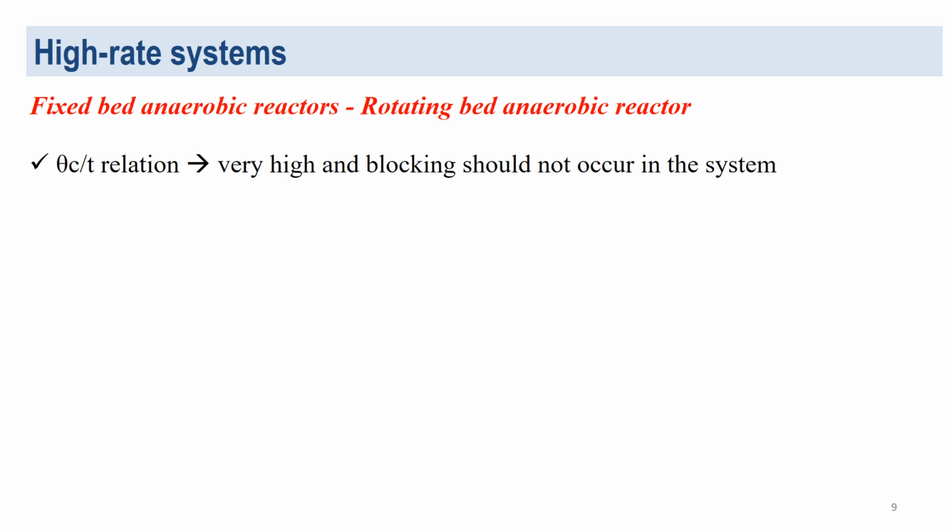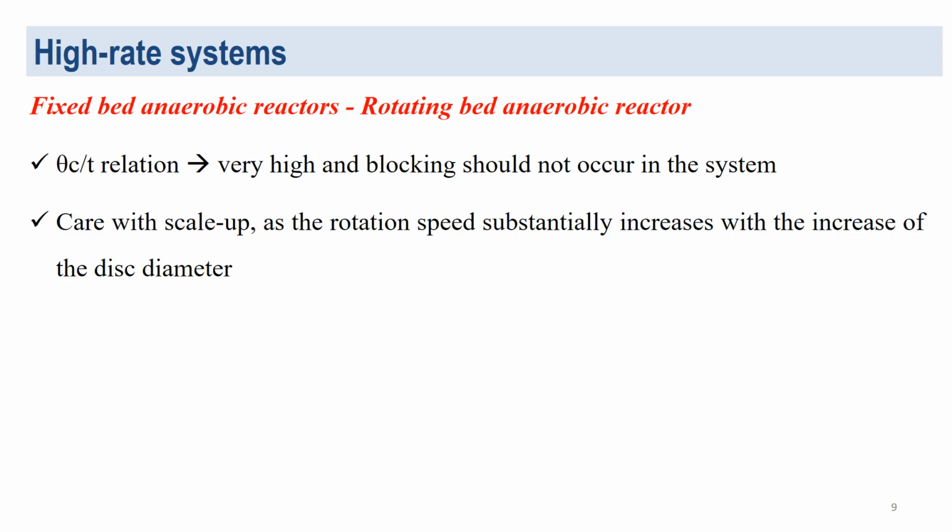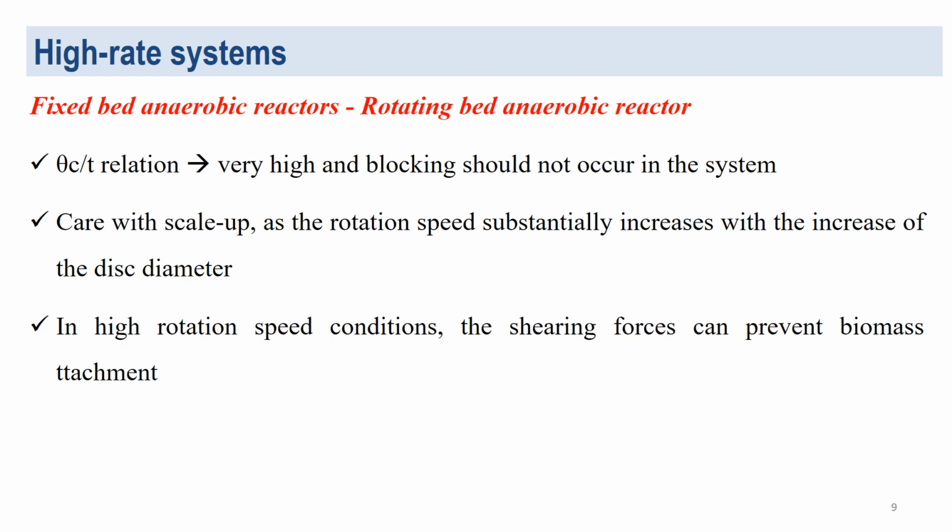The relation of solids retention time and hydraulic detention time is very high, and blocking should not occur in the system, since the rotation speed of the disks is such that the shearing forces promote the removal of excess biomass kept between the disks. However, care should be taken in the transfer of results obtained in the laboratory to full-scale plants in the scaling up, as the rotation speed substantially increases with the increase of the disk diameter. In high rotation speed conditions, the shearing forces can prevent biomass attachment.